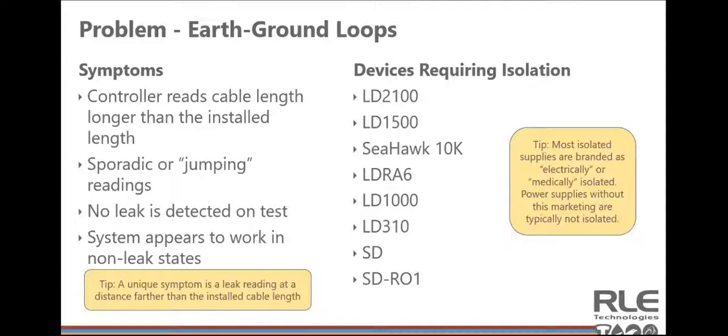And then I just wanted to reiterate the danger here: sometimes it might show up that the controller detects no leak at all, even if there's water on the cable. So that's definitely something to be cautious of. A number of our devices require isolation. RLE provides isolated power options, so we recommend you check our documentation and talk to our sales rep to make sure you're getting the correct equipment.